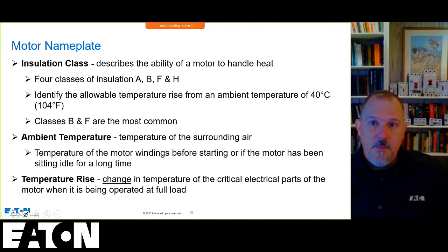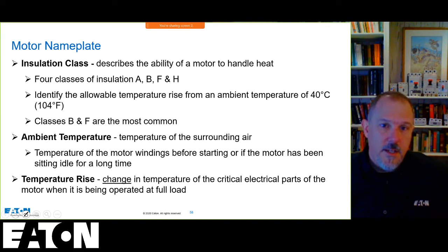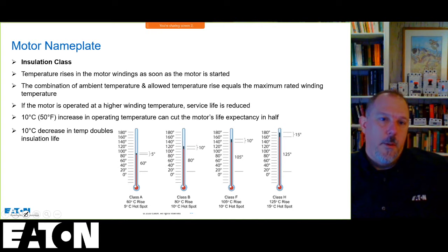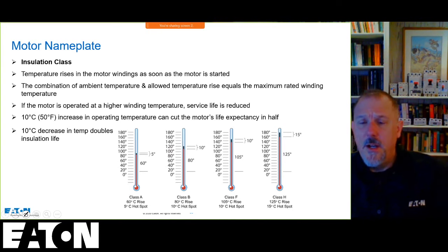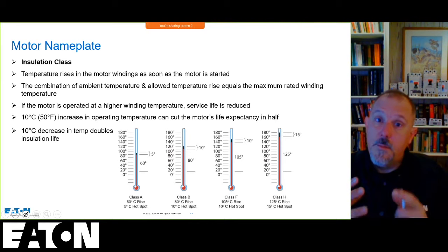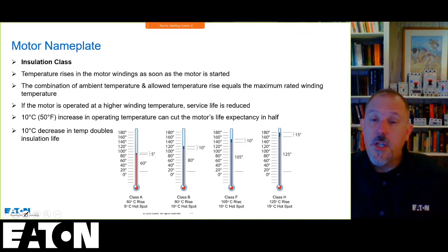And we just showed you that table, and it's important to understand that you want to preserve the life of that piece of equipment. This is why temperature is critical. So we have RTDs on the larger motors, your bigger investment. We're going to have RTDs, different types of temperature sensors, in and around that motor that are going to give you alarming and triggering and possibly shutting down that motor because of those temperature rises, to preserve the integrity of the insulation. Because it may not be a motor failure that contributes to the increased temperature. It could be something with the load that you're driving.